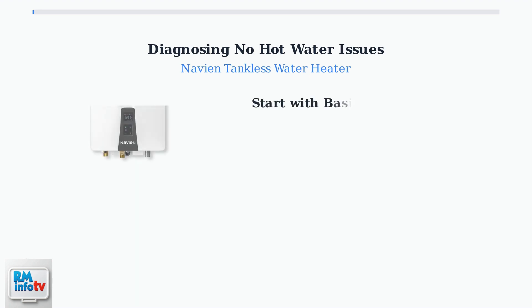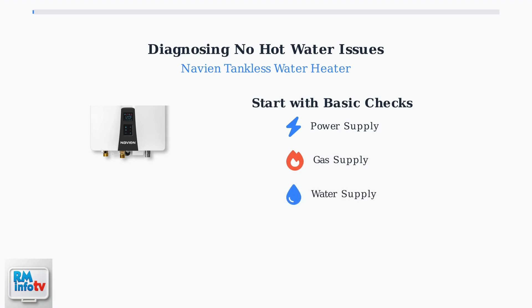Begin diagnosis by checking three fundamental requirements. First, verify the unit has electrical power and the circuit breaker hasn't tripped. Second, ensure the gas valve is open and gas pressure is adequate. Third, confirm water pressure is sufficient and inlet filters aren't clogged.